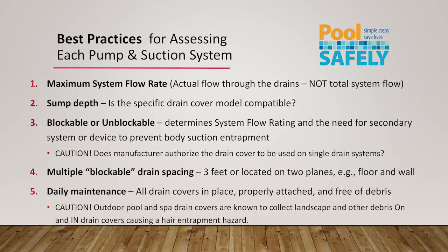It's kind of fun. So, best practices for assessing each pump and system: maximum system flow rate. You notice that one yet? Gotta know the flow rate. Sump depth. Is it blockable or unblockable? We need that to know if we need a secondary system. If we have multiple blockable drains, is the spacing 3 feet or are they located on 2 planes? So they can be closer together under Illinois law and the federal law. I didn't go into that detail in this video.